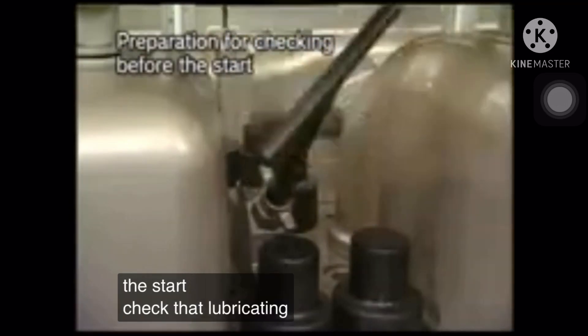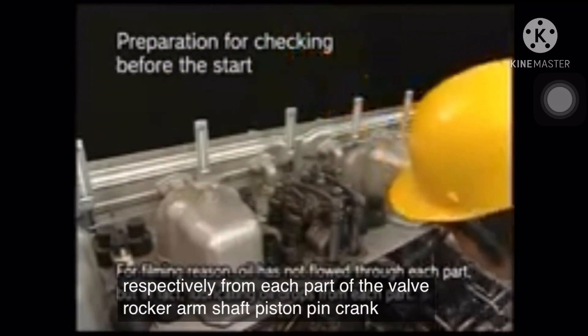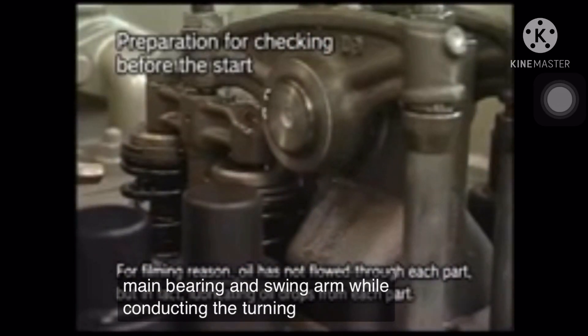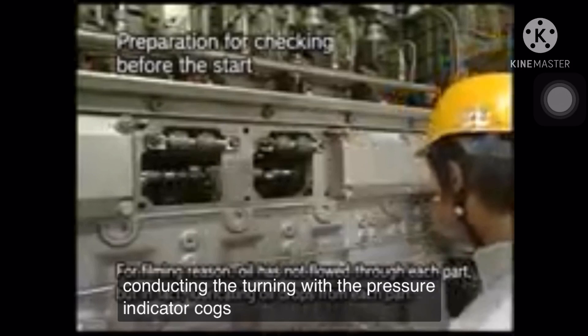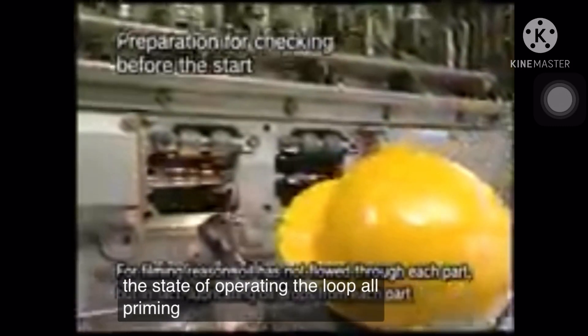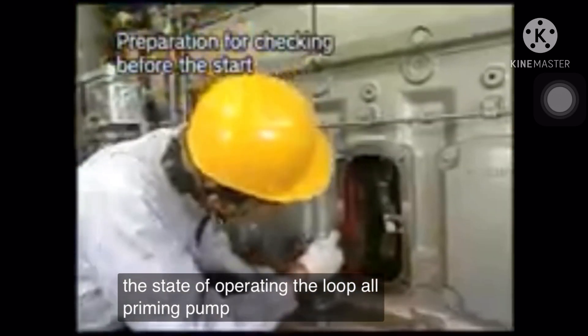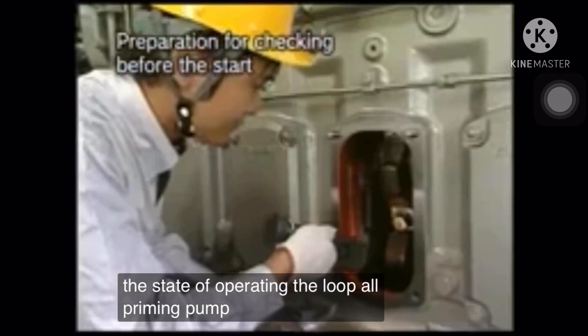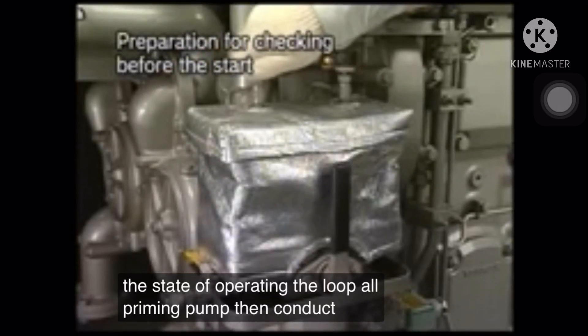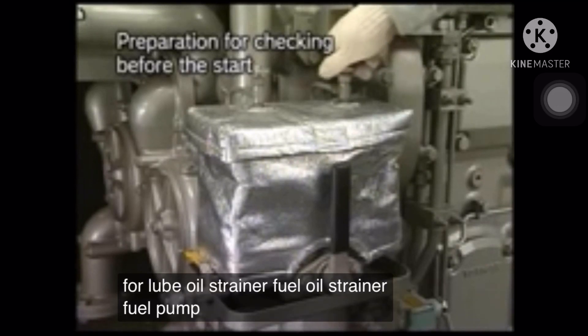Check that lubricating oil drops respectively from each part of the valve rocker arm shaft, piston pin, crank pin, main bearing, and swing arm while conducting the turning with the pressure indicator cocks of all cylinders open in the state of operating the lube oil priming pump. Then, conduct air bleeding for lube oil strainer, fuel oil strainer, fuel pump, and so on.